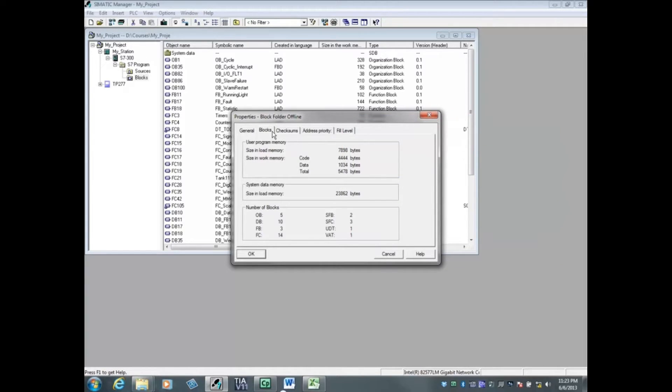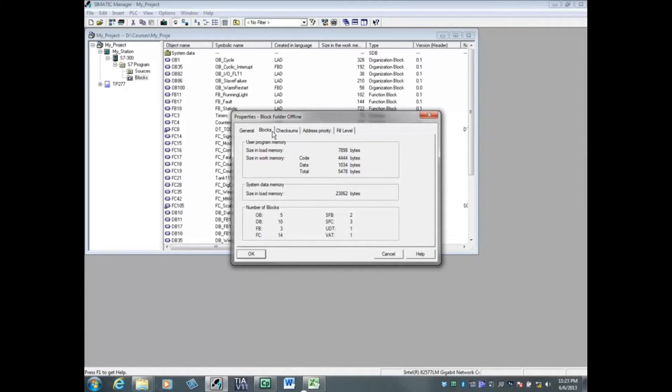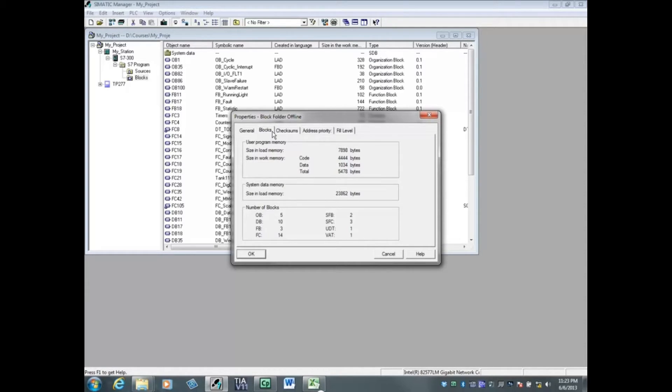The micro memory card should be at least 60% larger than this to have working room. A minimum one megabyte card would be needed. If you plan to store other documents or the archived project, the card will need to be considerably larger.